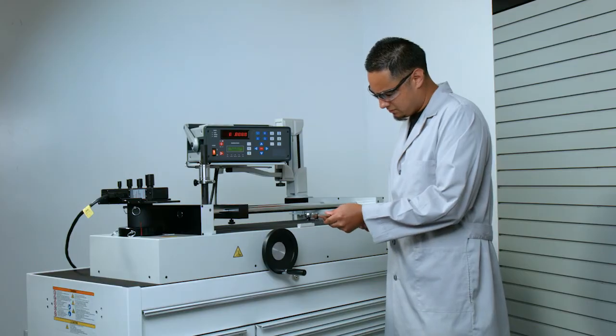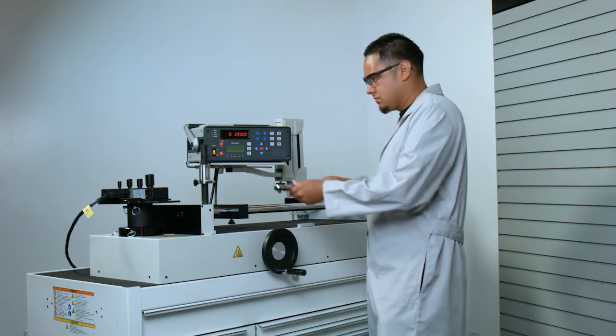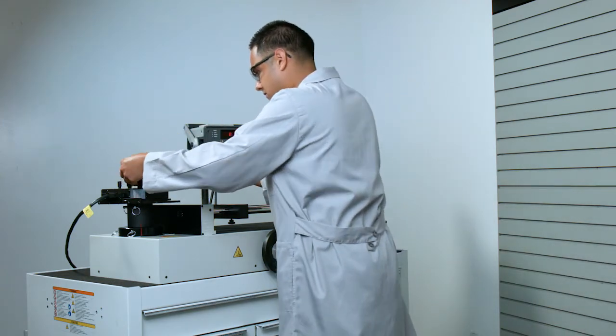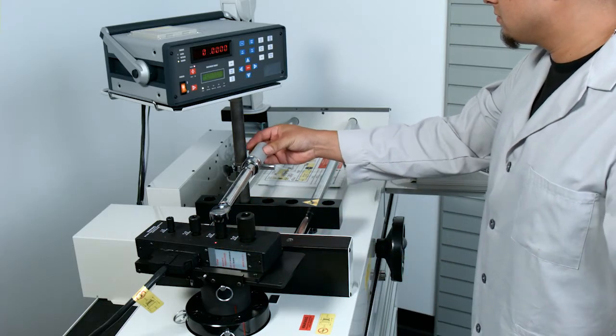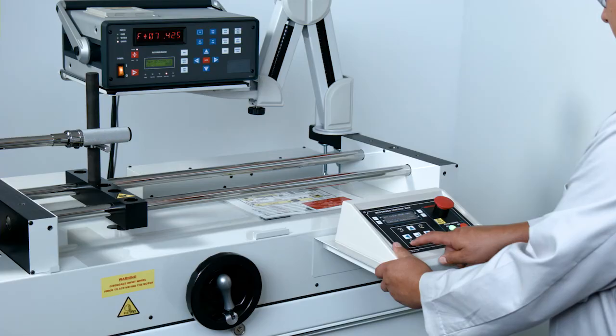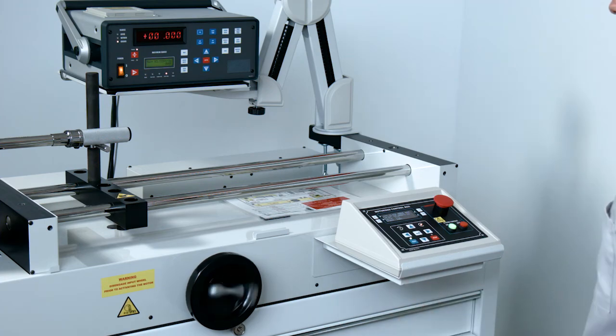A torque wrench, set at a specific value, is placed in the calibrator with the handle held stationary. The square drive is placed into the transducer with the handle held stationary. The motor automatically rotates the transducer until the wrench reaches its set point.